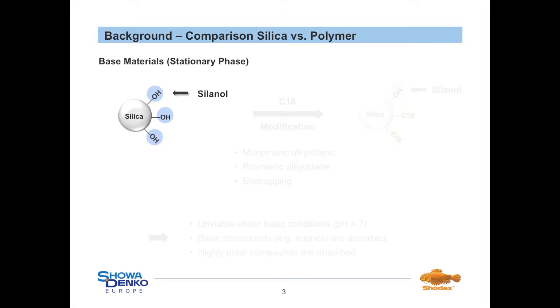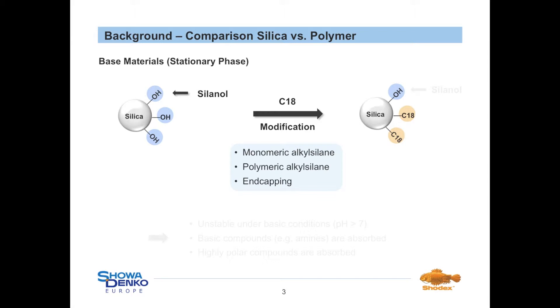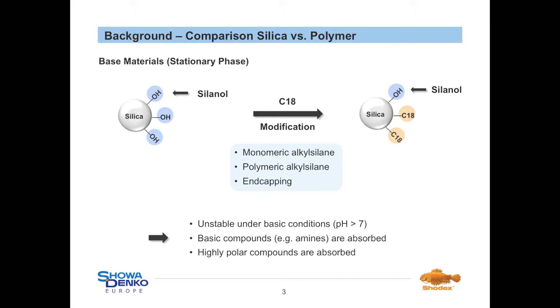Shodex's focus lies on manufacturing HPLC columns which consist of pure polymer-based stationary phases instead of silica-based ones. The most important reason is that polymer-based particles are chemically more resistant and offer a broader application range. For reversed-phase columns, there are methods to modify silica particles with alkyl chains, for example C18, using monomeric or polymeric alkyl silanes. Nevertheless, not all free silanol groups can be occupied by these methods, even after end-capping procedures, leading to high silanol contents and several drawbacks. Traditional silica-based reversed-phase columns are unstable under basic conditions, i.e. pH above 7, and adsorb basic as well as highly polar compounds.